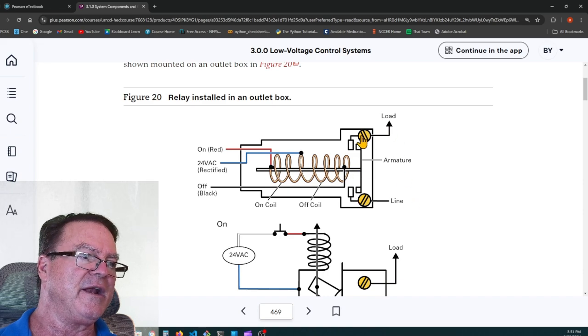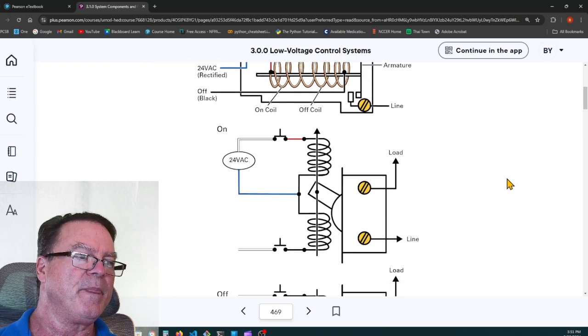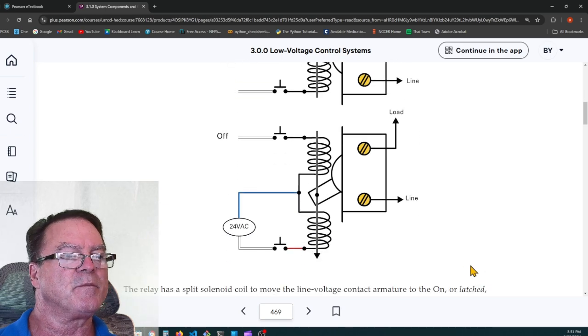You have your line and load, and when the signal comes to it, 24 volts AC, either on or off, it'll move this plunger to either make contact or break contact, and it goes from line to load. Here's the same thing, line to load. They have a two-position switch with 24 volts AC, and when you close the one switch, it pulls the plunger up, turning the lights on. When you operate the other switch, it pulls the plunger down and disconnects the switch.